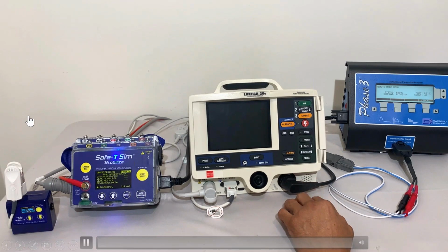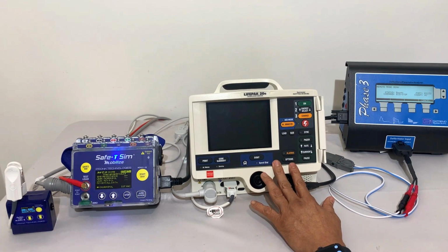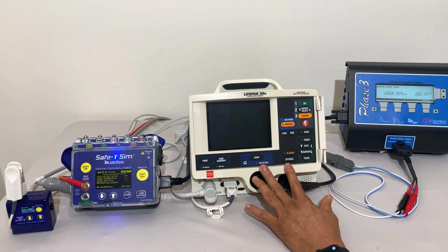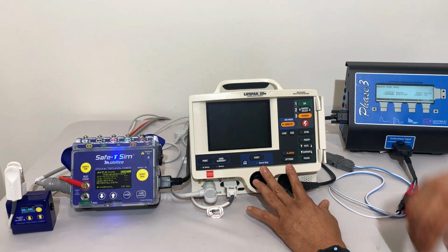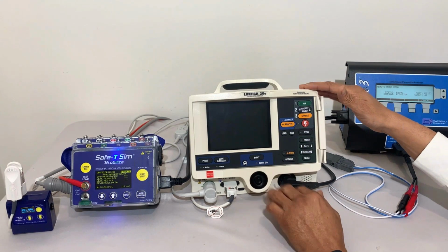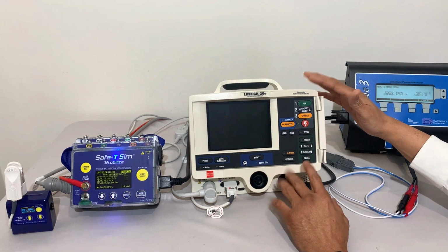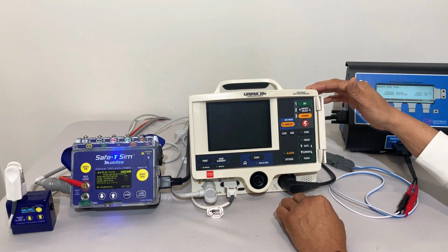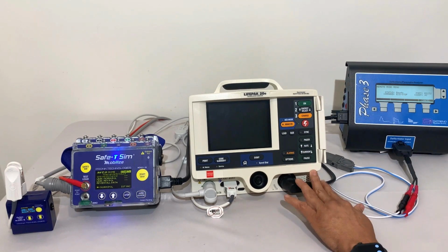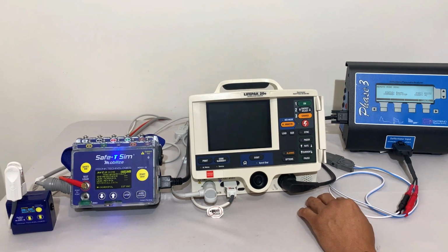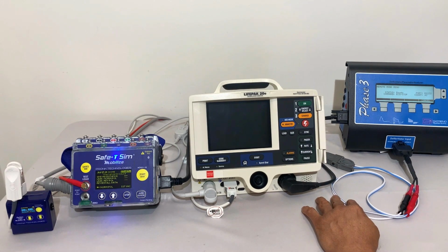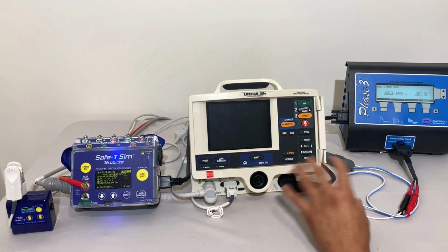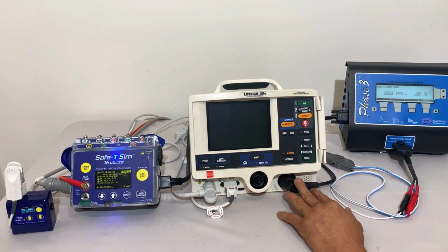We want to go ahead and get started on doing a service on this LifePak 20E. And really, before we connect anything up to the defibrillator, we want to make sure we do our physical inspection as required by the manufacturer. So they've stated to do a number of things. One of the most critical things, of course, is the visual inspection of the device itself. We really want to make sure we've done our physical inspection, looking for any damage to the device itself. Really important, could be an indication that there could be something wrong with the unit or it may not be functioning per the specifications. You want to shake it. They literally want you to shake the device, listening for any loose hardware. Any loose hardware inside the device, of course, can be a real hazard. So we want to make sure we've done that.